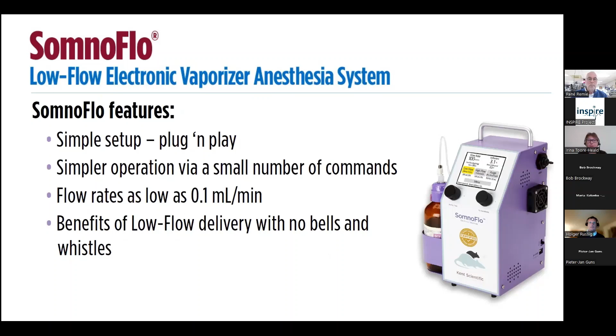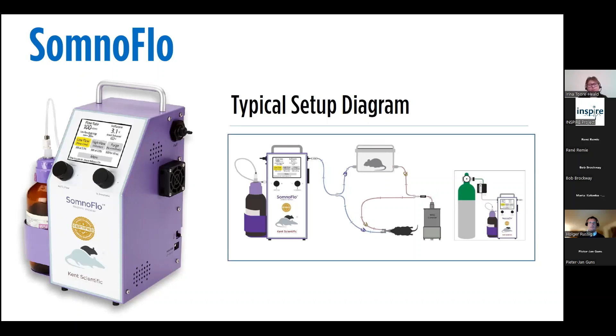SomnoSuite had a warming pad called RightTemp. SomnoFlo does not, but one should always practice safe experiments and use the warming. If you can have a look at this chart here, SomnoFlo is connected the same way, so that the tubing goes to either the induction chamber or the animal, whether it is on a face mask, a stereotaxic system, or the ventilator. And then the charcoal canister is incorporated to draw the waste gas.